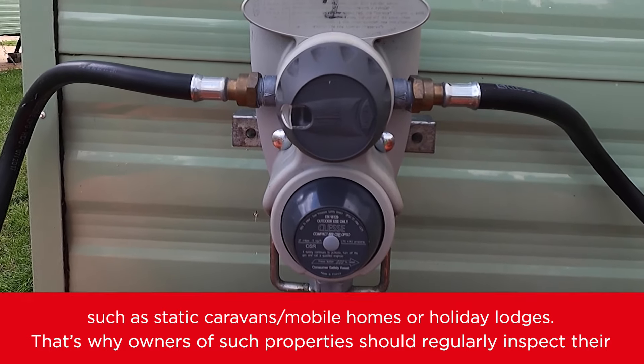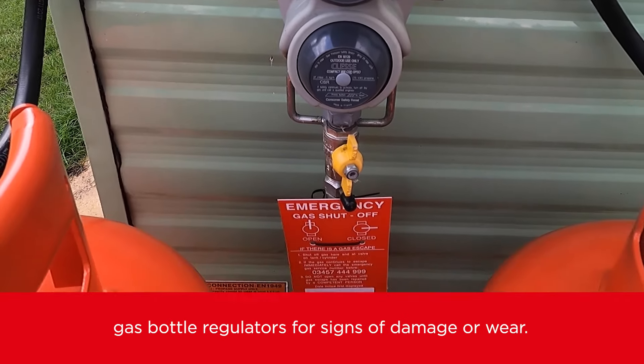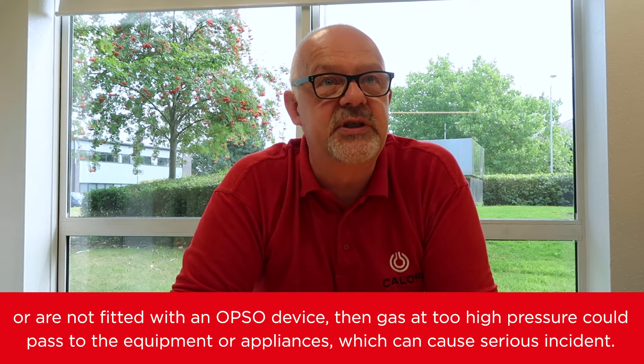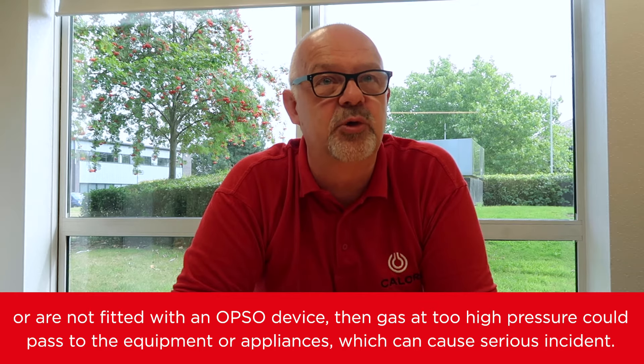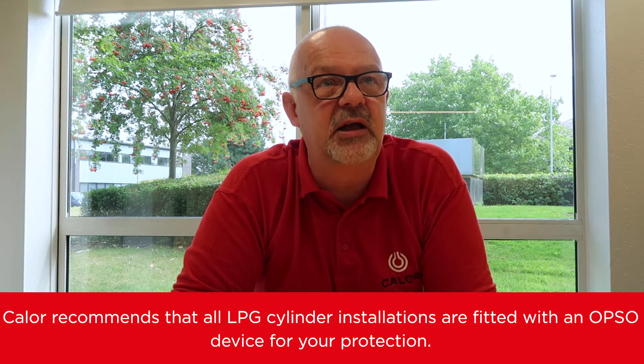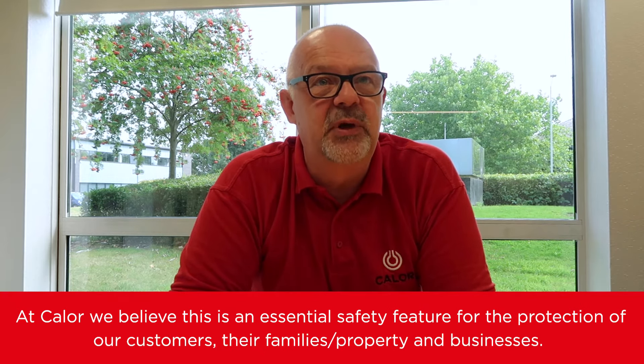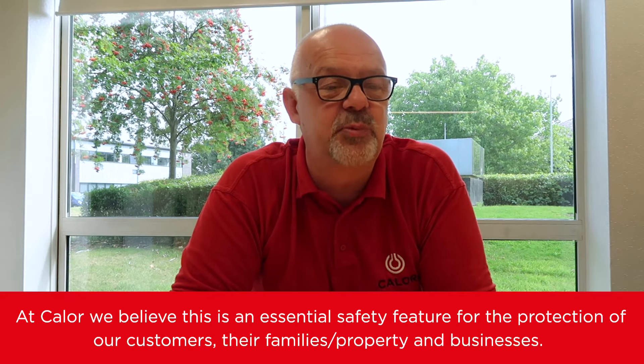That's why owners of such properties should regularly inspect their gas bottle regulators for signs of damage or wear. If the regulators are not used and maintained correctly, if they are 10 years old or older, or are not fitted with an OPSO device, then gas at too high pressure could pass to the equipment or appliances, which can cause serious incidents. Calor recommends that all LPG cylinder installations are fitted with an OPSO device for your protection, as we believe this is an essential safety feature for the protection of our customers, their families, property, and businesses.